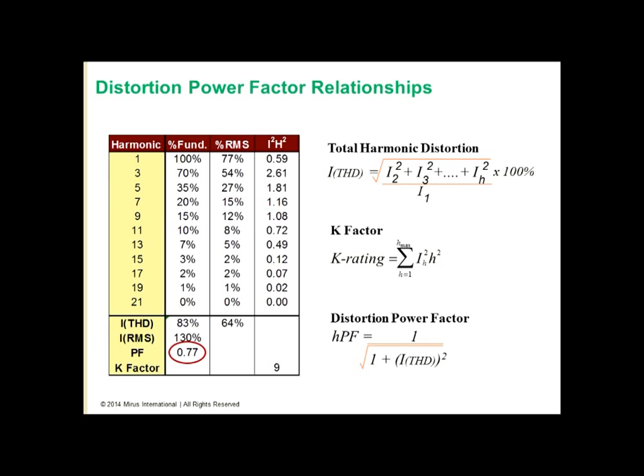And finally, distortion power factor is defined as 1 over the square root of 1 plus the total harmonic current distortion squared. So when we do that calculation in this example, the power factor is 0.77. So this particular load profile has a total harmonic current distortion of 83%, a K factor rating of 9, and a power factor of 0.77.